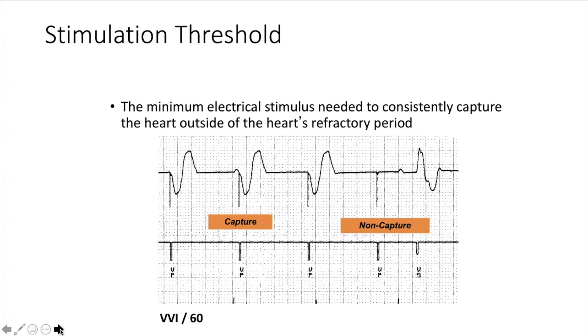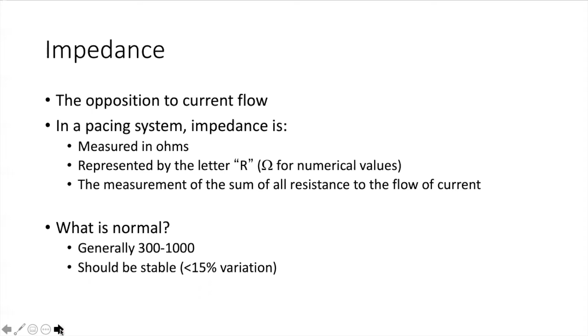Impedance is the sum of all resistance to the flow of current, meaning it shows the opposition to current flow. In the pacing system, impedance is measured in ohms, and generally normal is around 300 to 1,000, and we use this mainly to look for stability. Very large fluctuations in impedance, or drops or increases, can suggest lead malfunction.